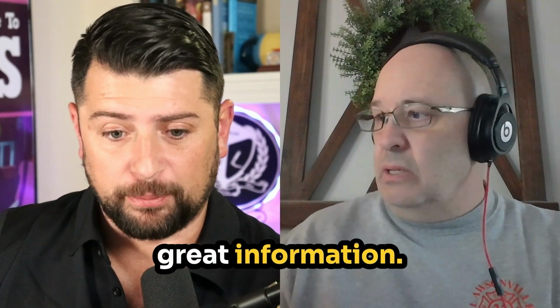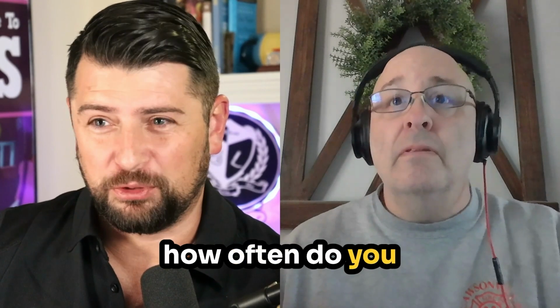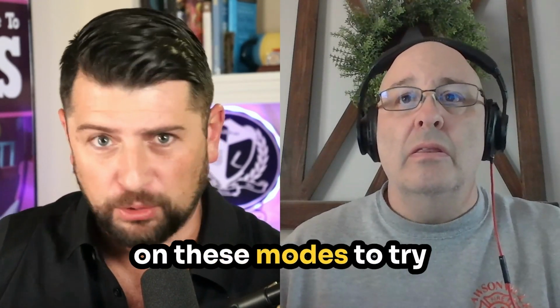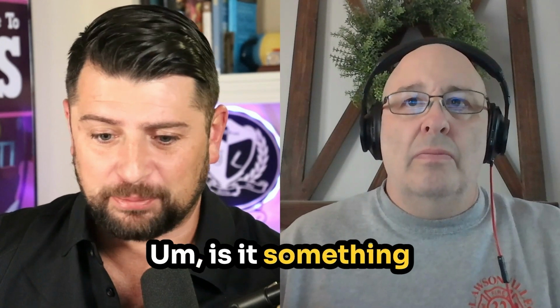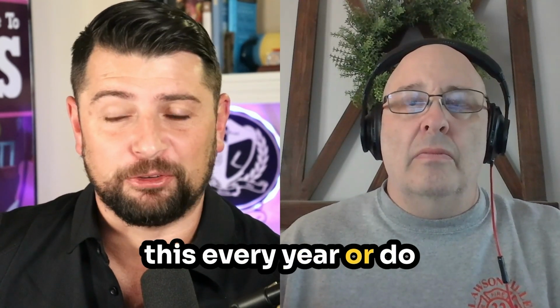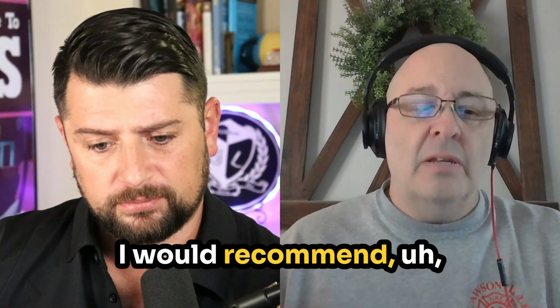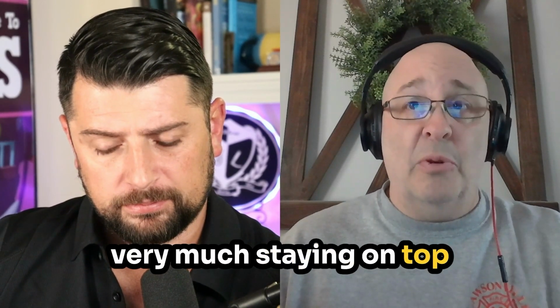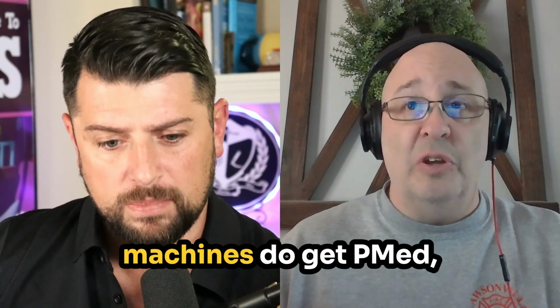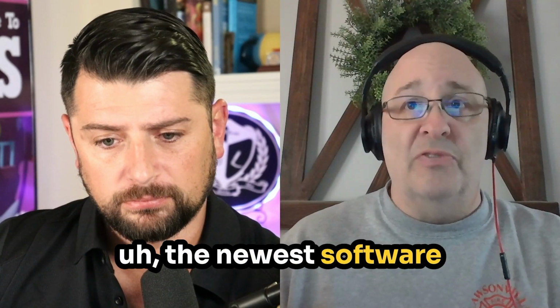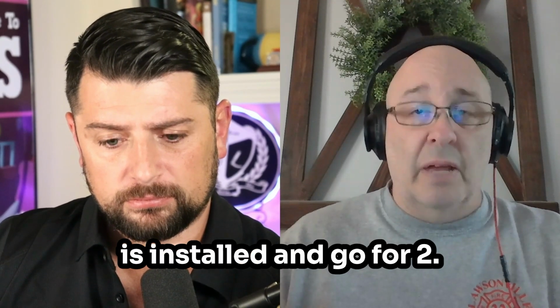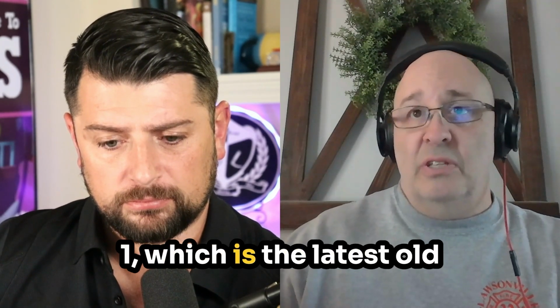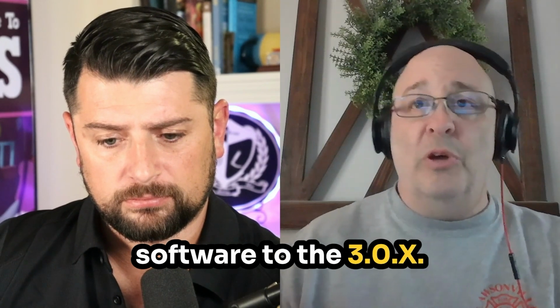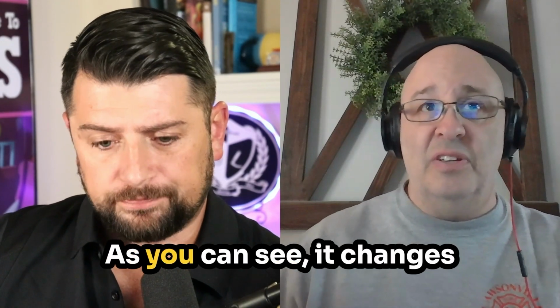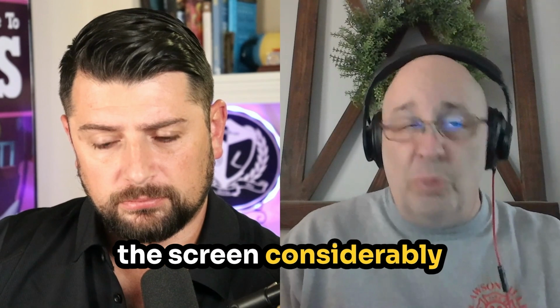Awesome. No, that's great information. How often do you guys update that? Because it sounds like you're always working on these modes to try to make them better. Is it something where you should update this every year, or do they send out messages when they do an update? Yes to both. I would recommend very much staying on top of your biomedical group, so when your machines do get PM'd, the newest software is installed. And going from 2.2.1, which is the latest old software, to the 3.0.x, that is a big jump. As you can see, it changes the screen considerably.